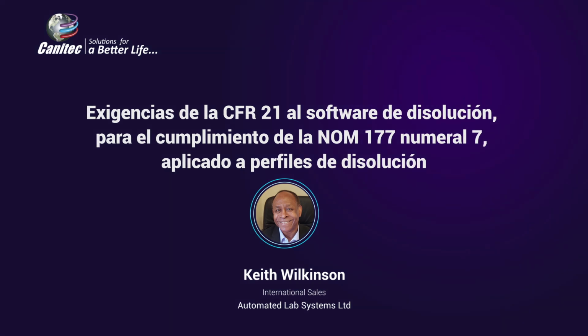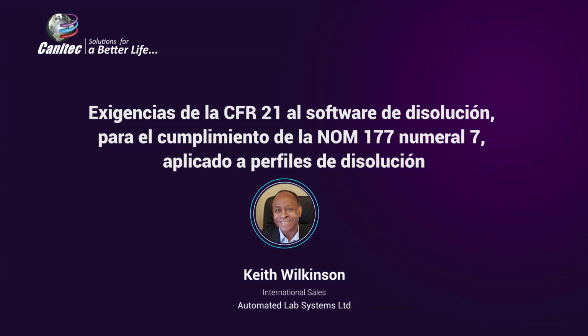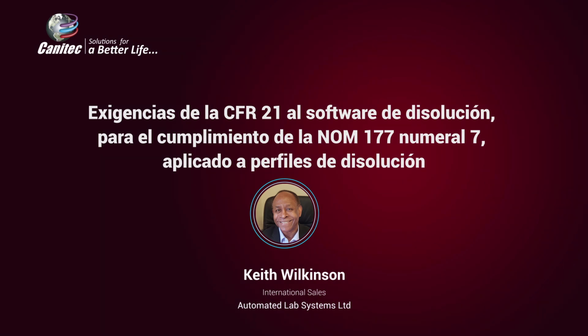Here I have defined that our data record needs to be signed. I've defined an analyst group and a supervisor group. These you can name yourself. This could be in the Spanish language, for example. And if you wanted to, you can create other levels. Up to 5 levels can be created for signing.